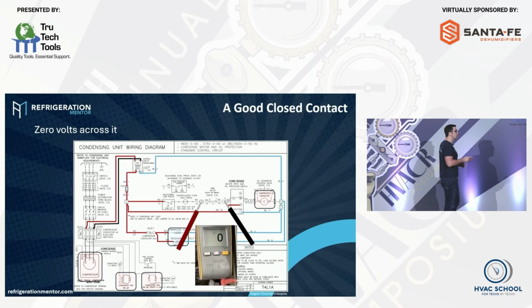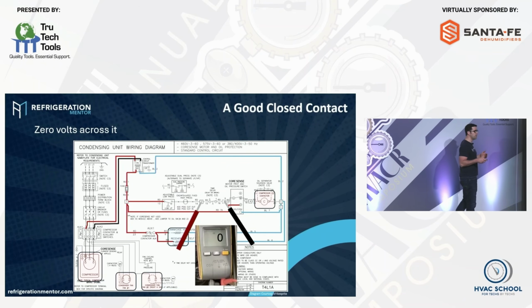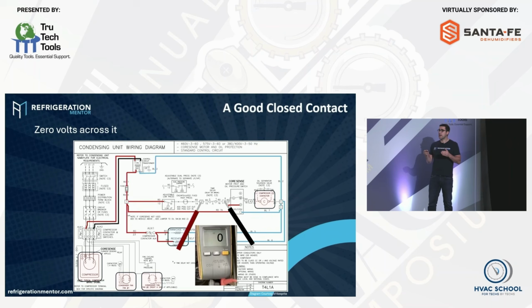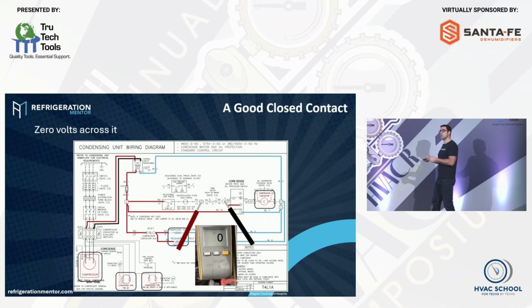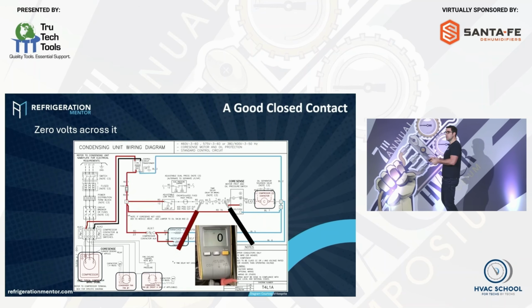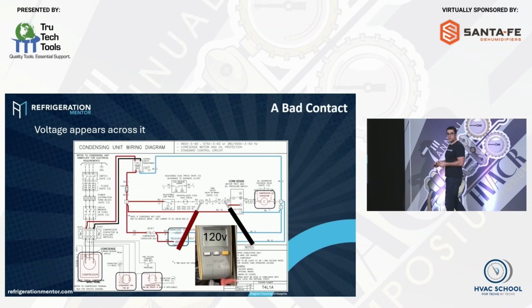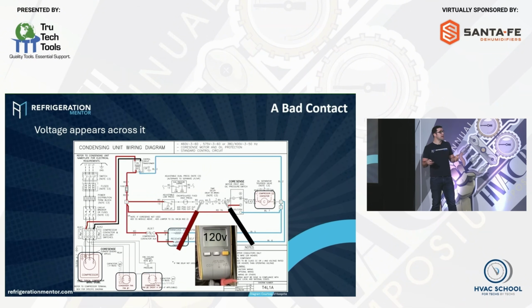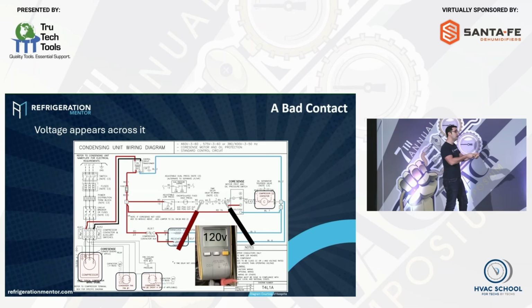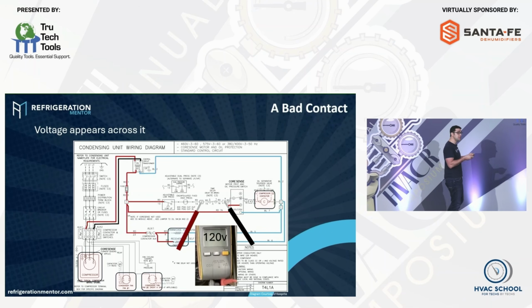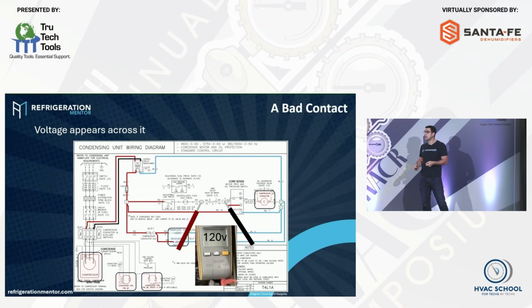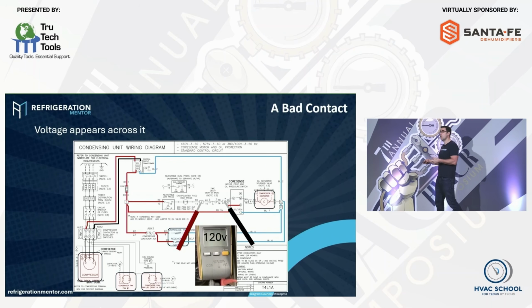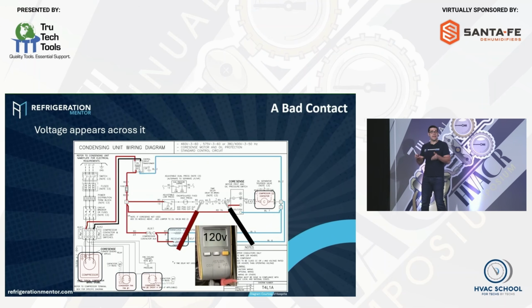A good closed contact, what does that really mean? If we have power to a circuit and we have a switch and we go across that switch, what do we get? We get 0 volts. Okay? If that switch now is open, what do we get? We get potential. This is what it's called, potential. We get whatever that circuit voltage is, 120 volts in this example. So if it's closed, you get 0. If it's open, it's 120. We are testing that switch.